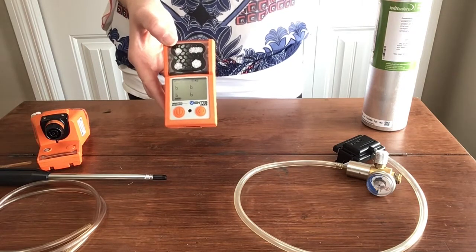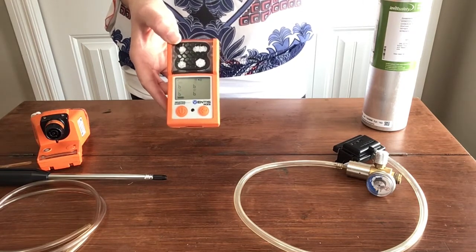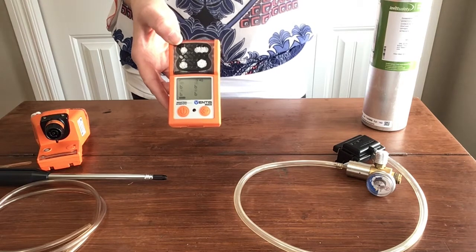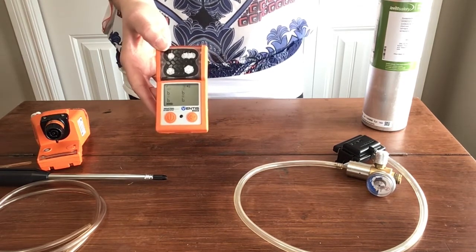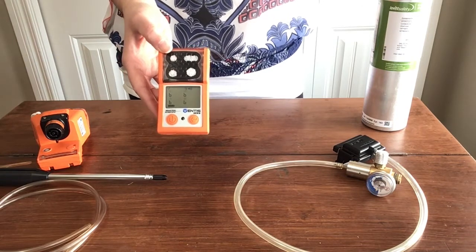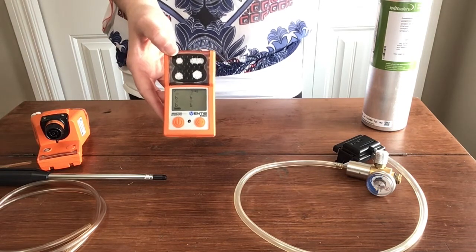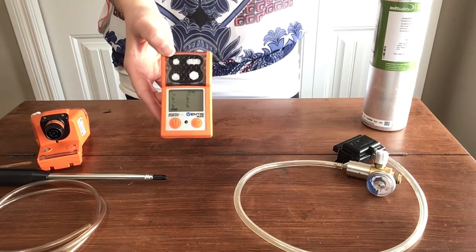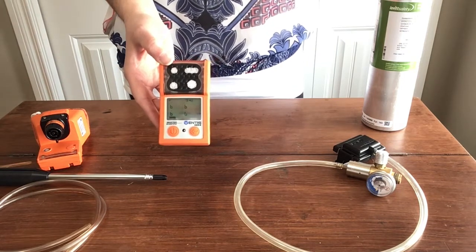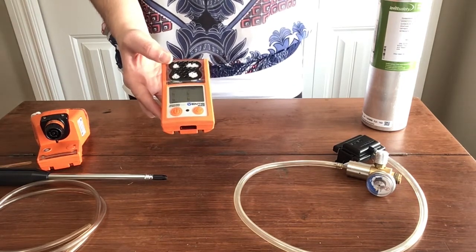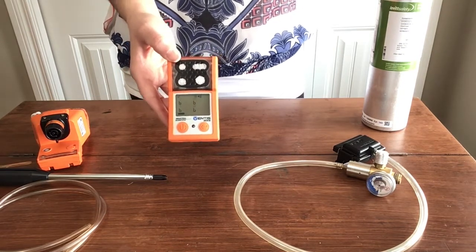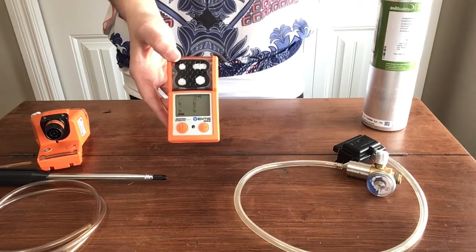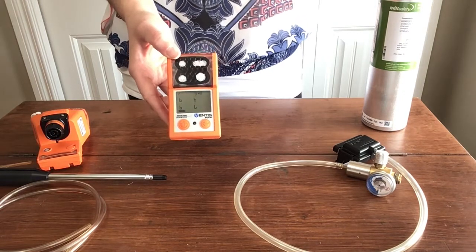Now, in addition to a monthly calibration, your workers are going to do a pre-use calibration, also known as a bump test. Okay? A bump test is recommended by CSA every time before this is used. It is also recommended by Ventis, the manufacturer, every time before this is used. And so because of that, we need to make sure that our workers are doing a bump test every time they go to take this into the field.